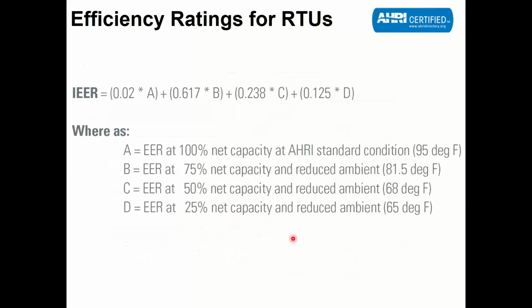Here's how we calculate IEER for those that care. We actually measure 4 different operating points. There's one at 100% loaded, one at 75, one at 50, and one at 25% capacity, essentially. And then what we do is take those efficiency numbers and we give 2% weighting to the full load number. We give 62% to the 75% number. We give 24% to the 50, and we give 12% weighting to the 25. The reason we give less over here is because we're probably going to be in an economizer mode for a lot of these systems, and we'll talk about economizers in a little bit. That's why we don't give much weighting and much thought to that. So we heavily load this middle section over here.